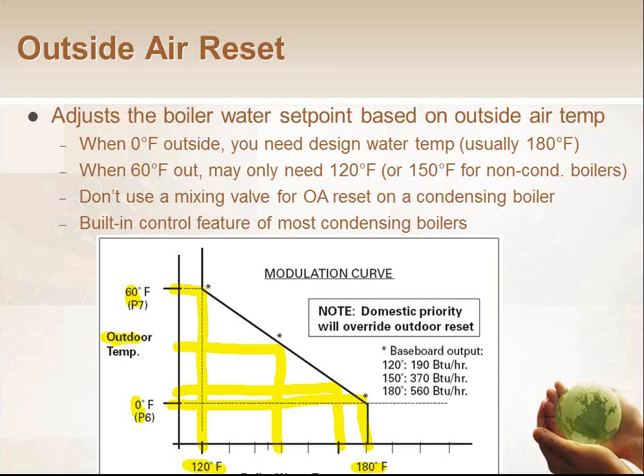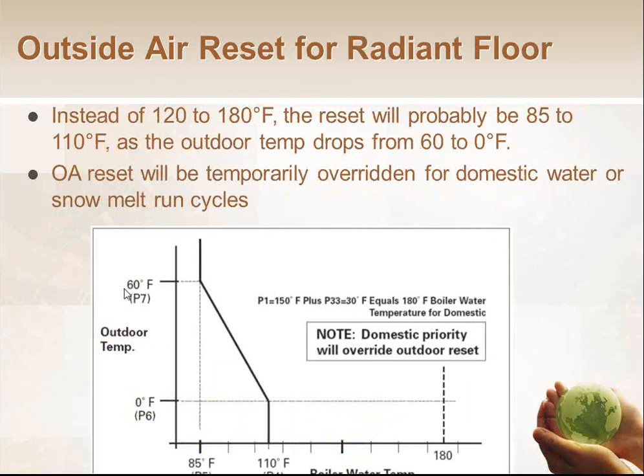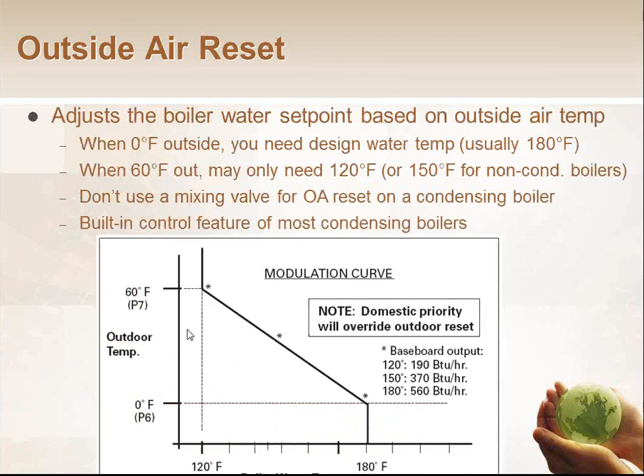Right? So I've got to tell my boiler two different things. I've got to tell it when to start and what temperature to operate at: 60 degrees, 120, and when to stop doing the reset: 0 and 180. And anything in between there, the boiler will figure out on its own. The vast majority of condensing boilers from most manufacturers nowadays include outside air reset control built into the boiler control itself. Now you still have to mount the outside air sensor, but everything else is already built into the boiler, right?